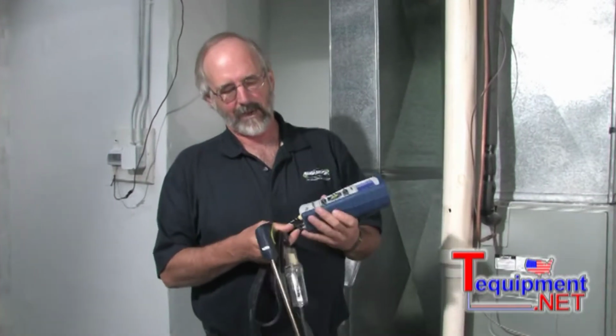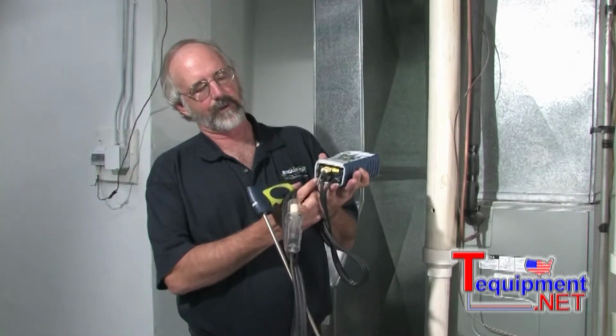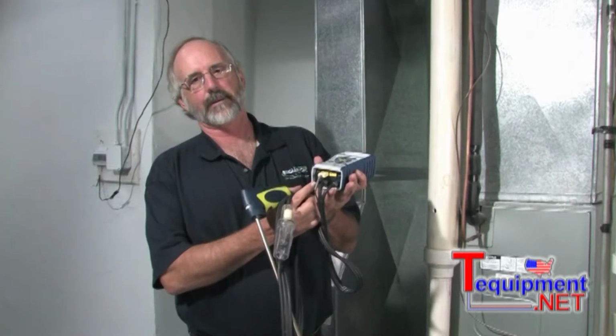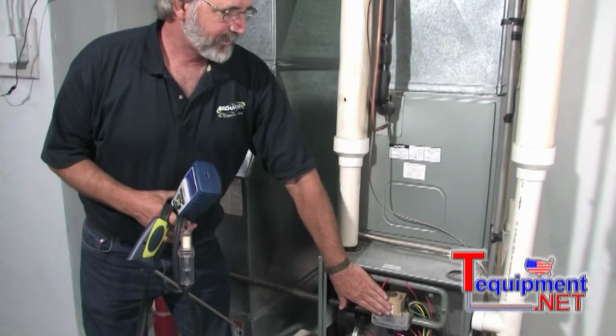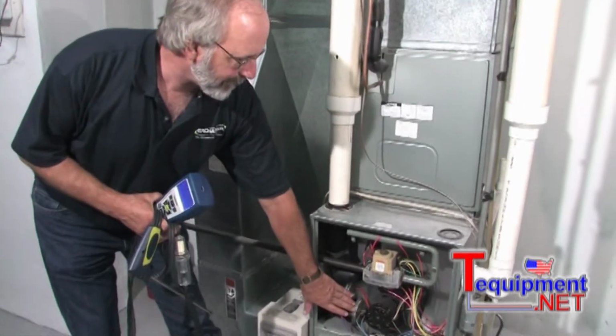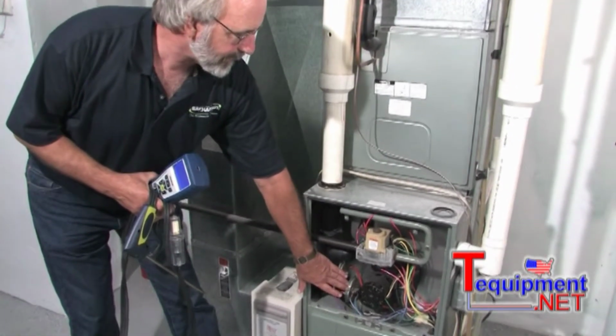Again, keep in mind this instrument is not only a combustion analyzer. On the bottom of it here, there are two ports for the digital manometer that's included. And on this particular piece of equipment, we can use that digital manometer to check the gas pressure, set up the gas pressure. We can also use that digital manometer to test for maybe a faulty pressure sensor.